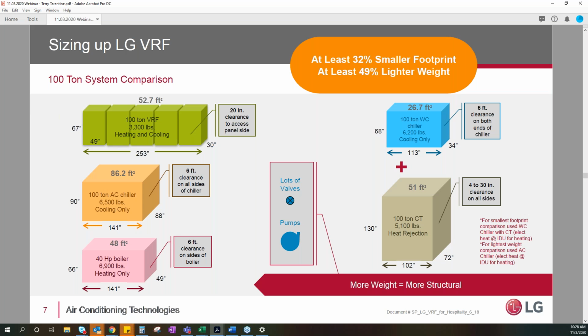Here they're just talking about footprint and weight. When you're putting these up on roofs of buildings, especially when we're doing a retrofit job, maybe the building's been abandoned for a long time. I think the David Whitney building in Detroit was a good example. It was abandoned for 20 years. Roof had not been maintained. So weight was an issue on what we put there, and we were able to spread the weight out with the VRF system and managed to heat and cool that building completely using nothing but heat pumps.